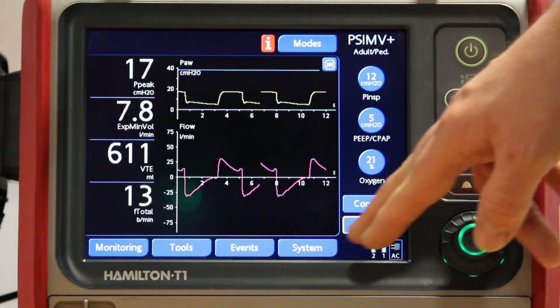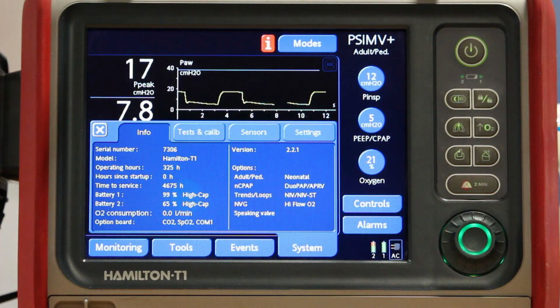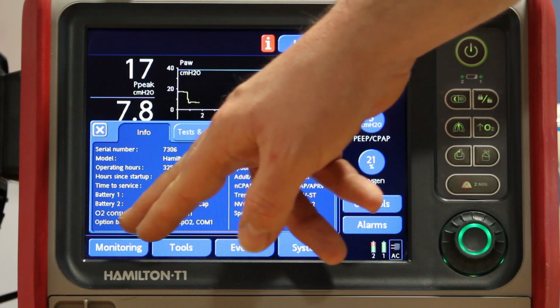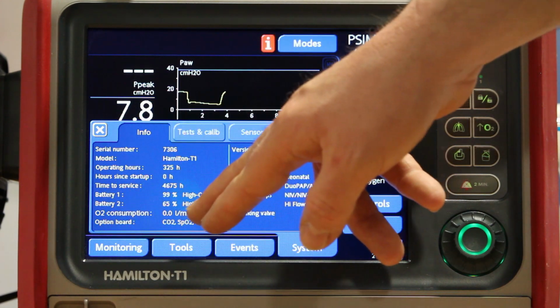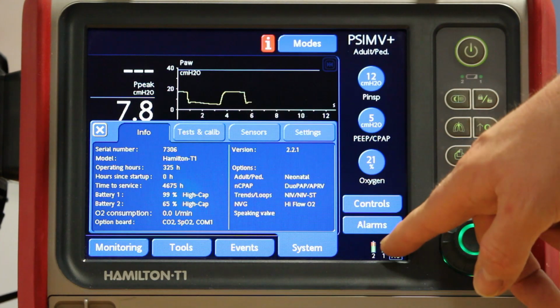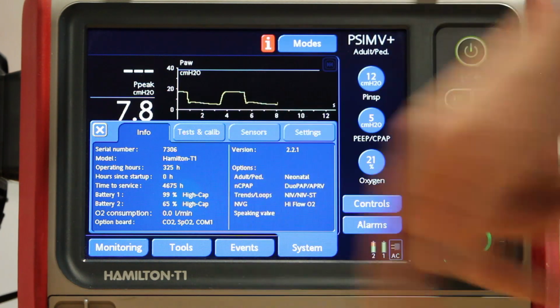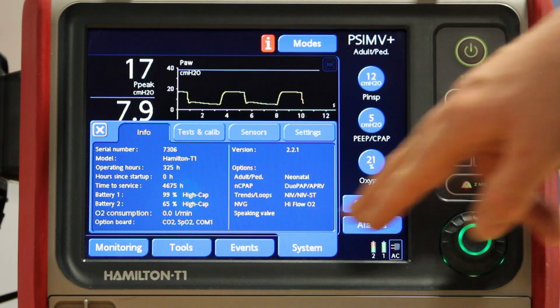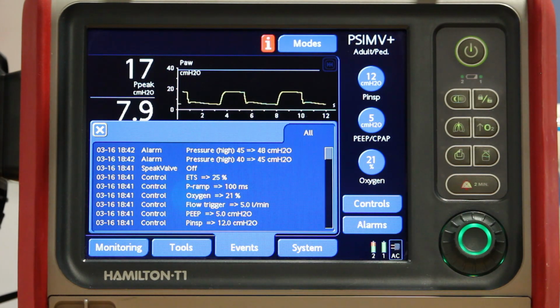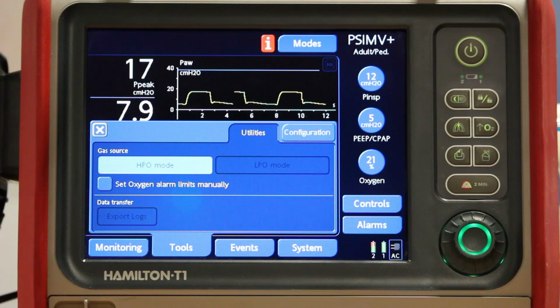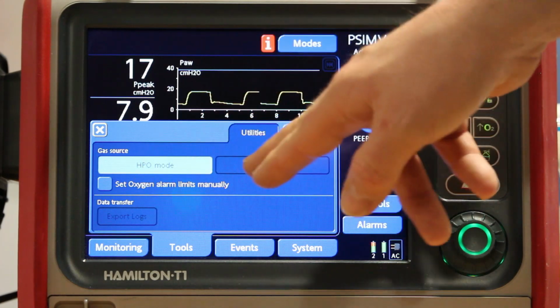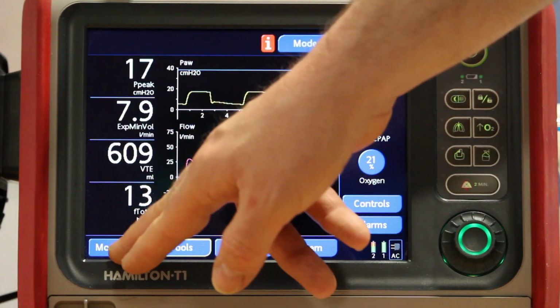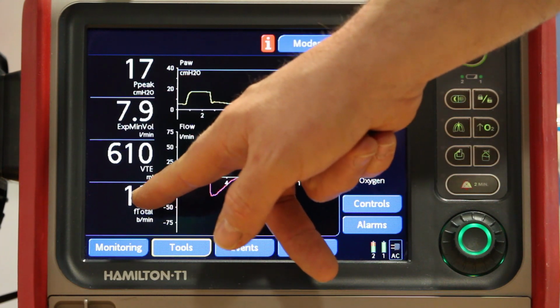So that is alarms. System then is all the information on the vent. I've got how much O2 I'm using here. I've also got a percentage charge on the batteries. Now I've got a visual indicator here, but also a percentage charge, so I know exactly how much battery I have left. Events is everything that we've done since we turned on the ventilator, every adjustment that we've made. And tools, you can ignore tools, is for switching from high pressure mode to low pressure mode. And then we've got our main monitor parameters here on the side.